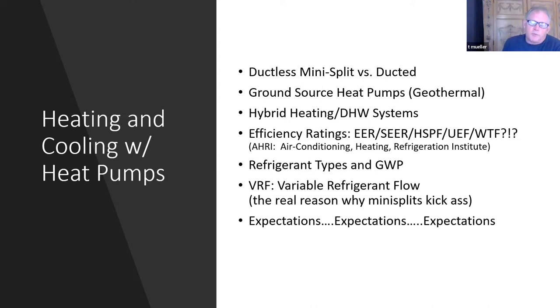It's important to prep people for that because, based on experience, we put in new heat pump systems and get a call immediately that they think it's not working. But it is working - it's just working at a very slow speed with warm air moving. In fact, warm air moving past you can actually feel cold if it's not much warmer than the ambient temperature of the room.